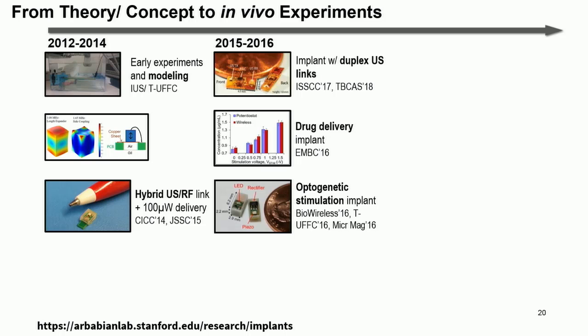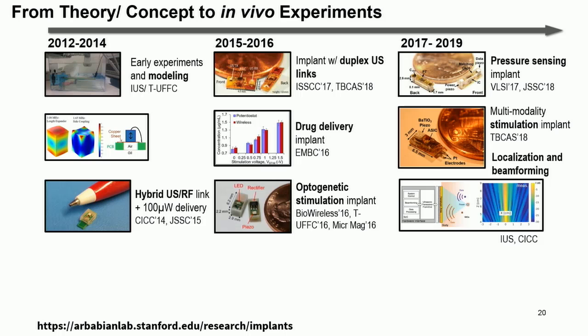The second generation devices were all about function. So we took a lot of the functions that were out there in implantable systems today with RF, and we tried to translate that into ultrasonic systems. The first one is implants for duplex communication, so we can do communications uplink and downlink. We can release drugs. This was a collaboration with the biochemistry department. And we can do optical stimulation for optogenetics. So that was the second generation. The third generation got into more complex functions. So we're thinking now about pressure sensing. This requires a high precision electronic system built into the implant. This is about a 10-bit resolution pressure sensor. I'm going to talk about that today. Multimodality stimulation, so we go to controlled stimulation as opposed to this one here, which was direct stimulation.